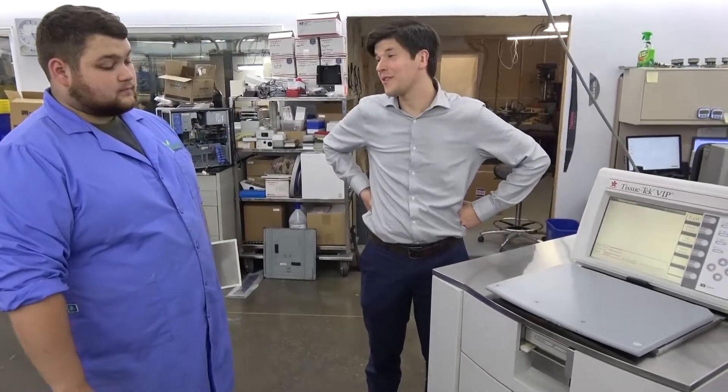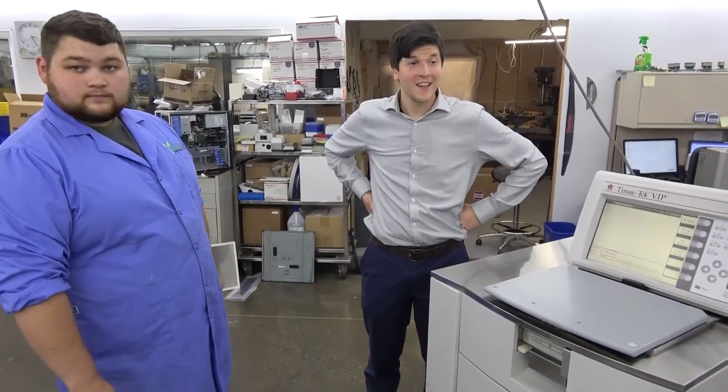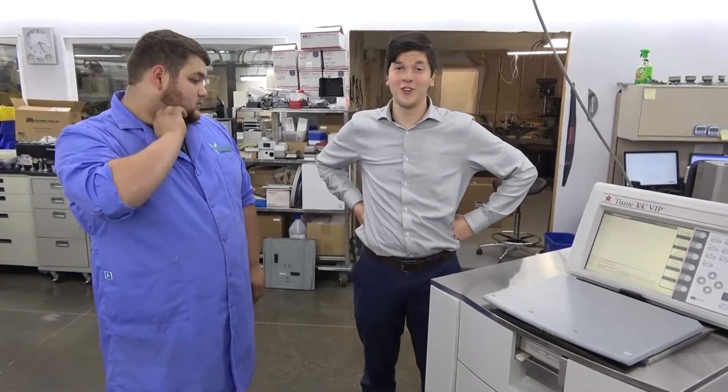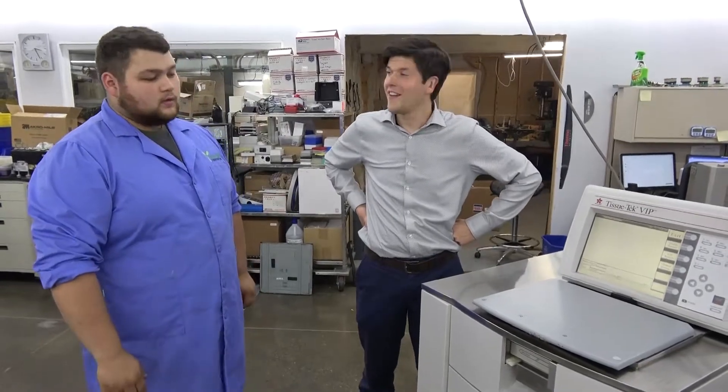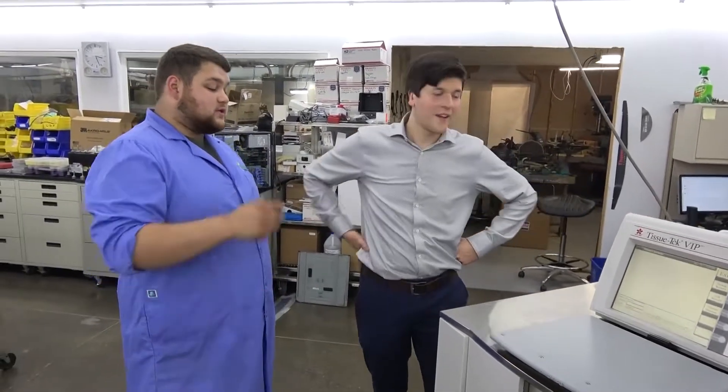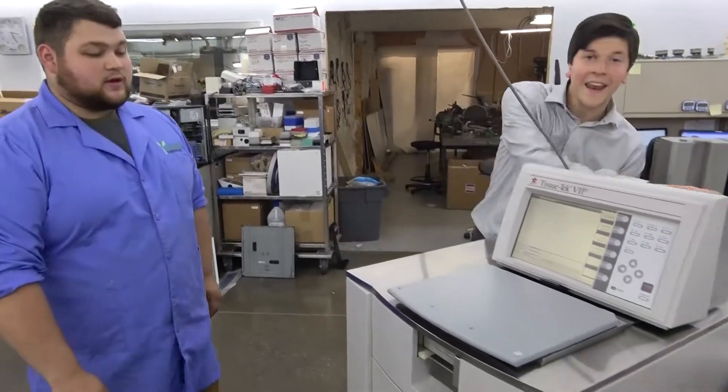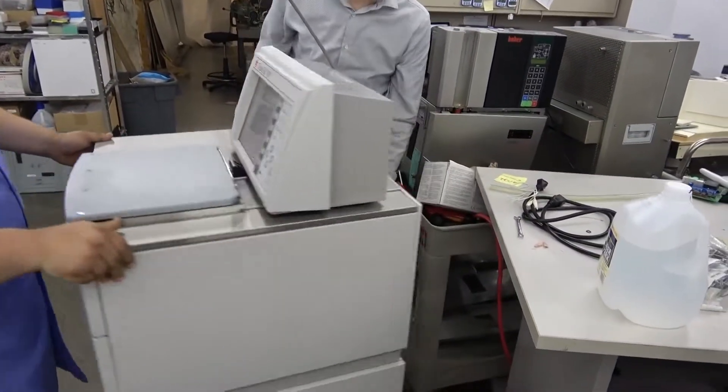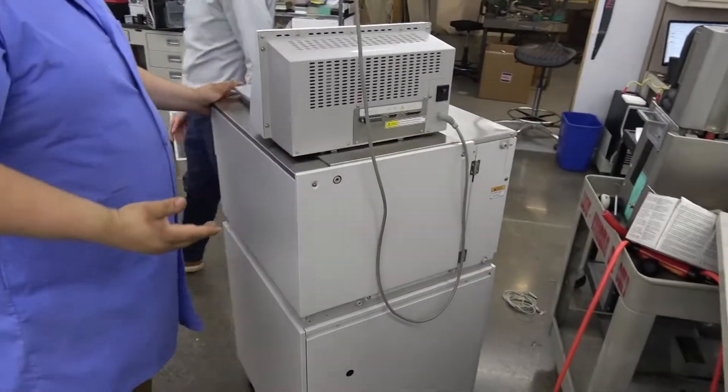And we got her working and functioning pretty well. Sometimes cleaning is the magic with a tissue processor. Yep. Converting. Yeah, well we're going to get to that. They put an internal electrical conversion in this thing, right? Yeah. Did you step it up to 220 or down to 110? Down to 110. So this is a 220 unit that has been converted. This corner, it's got an internal conversion.